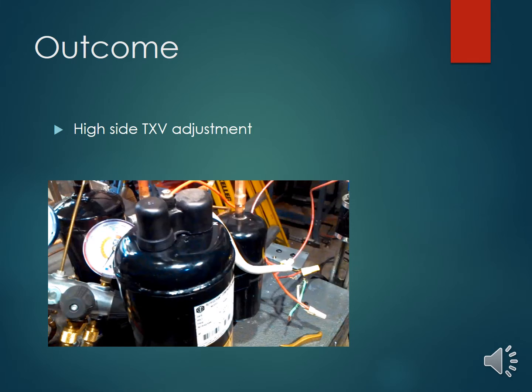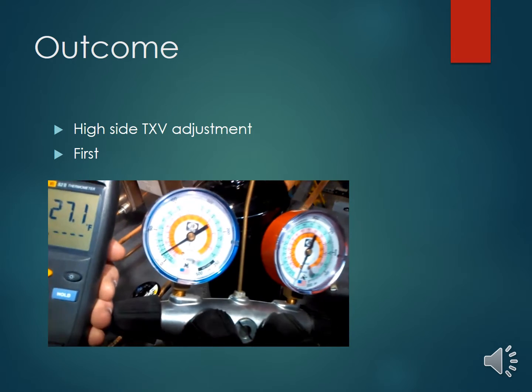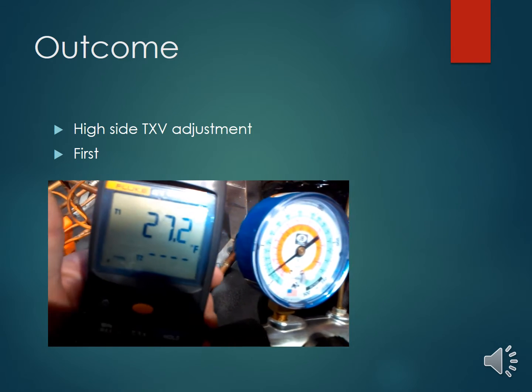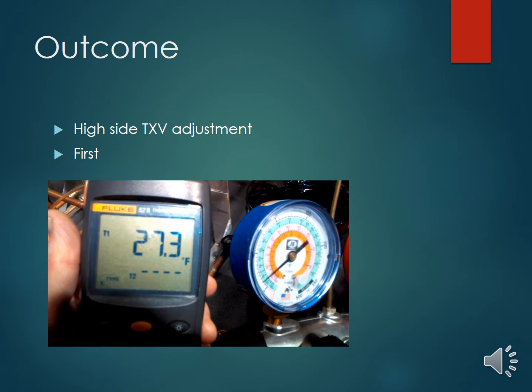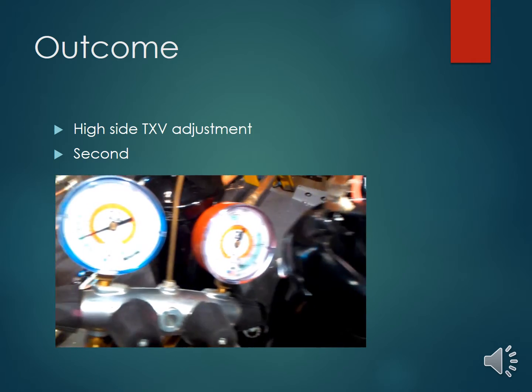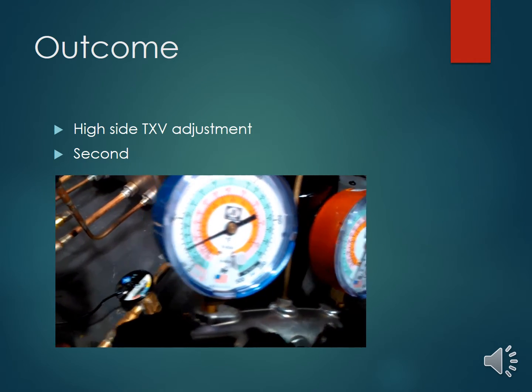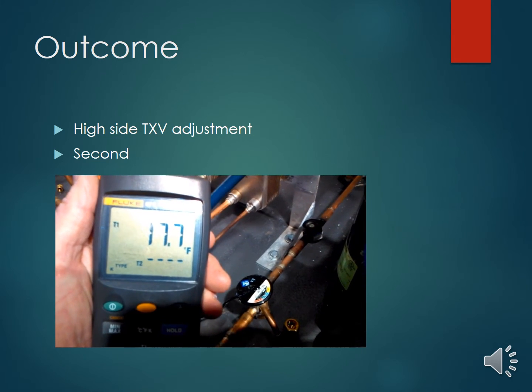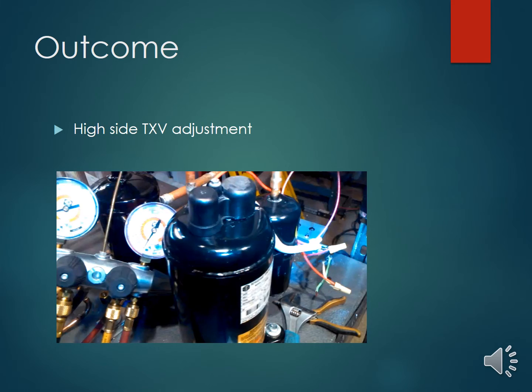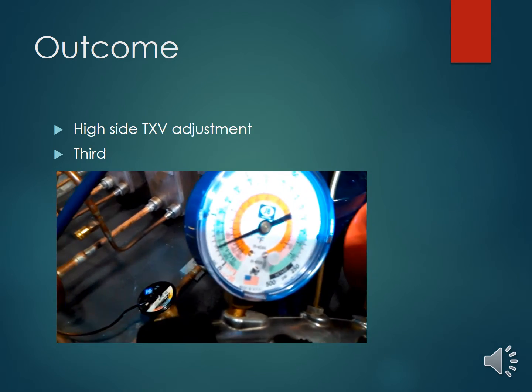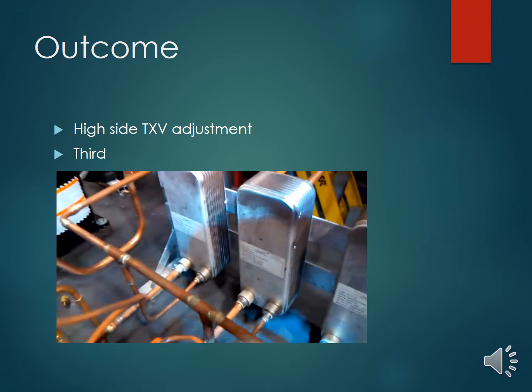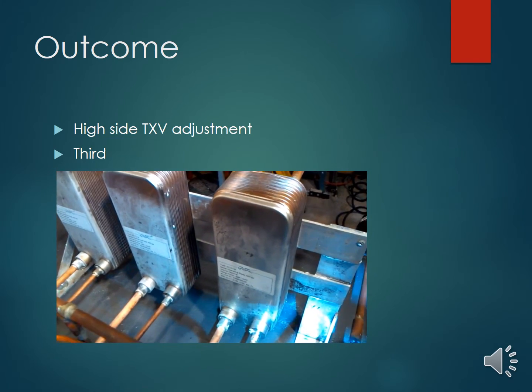As the high side was run, adjustments were made to the thermal expansion valve to try to achieve the correct amount of temperature within the interstage heat exchangers. This is the first try. This is the second adjustment on the high side expansion valve. This is the third adjustment made to the high side expansion valve. This is the lowest temperature that was able to be achieved. Frosting can be seen on the interstage heat exchangers.